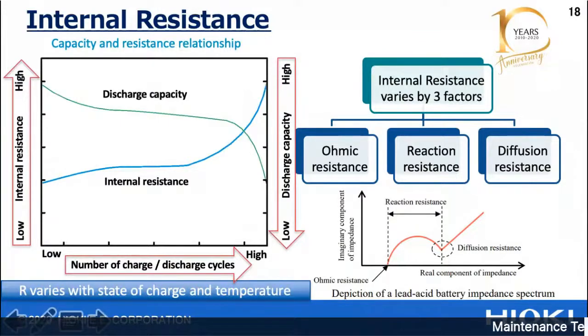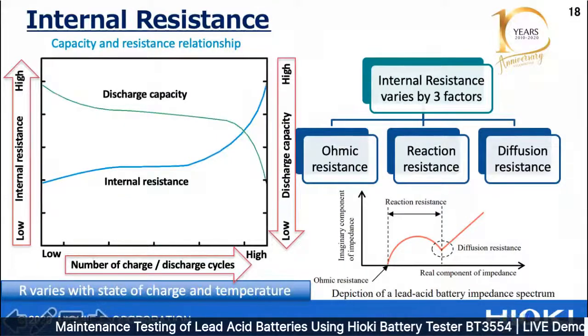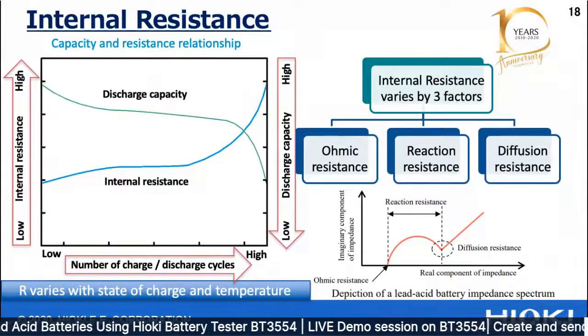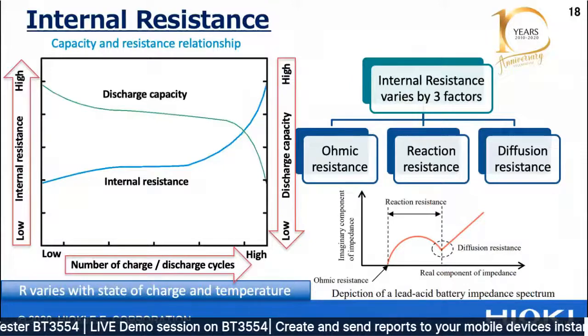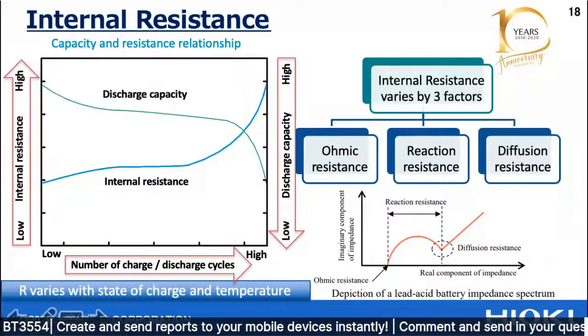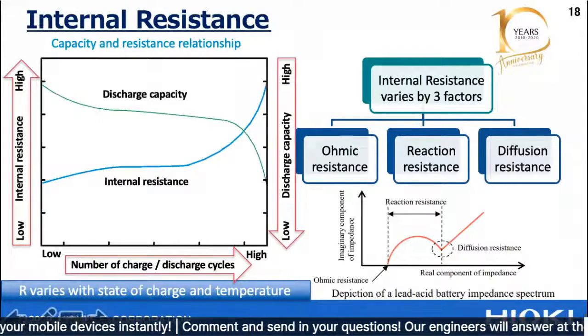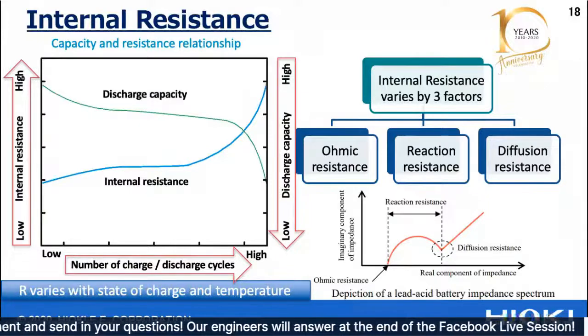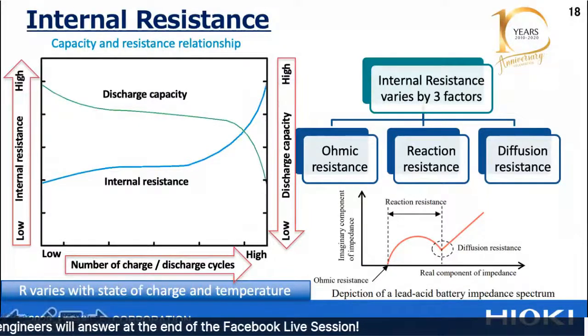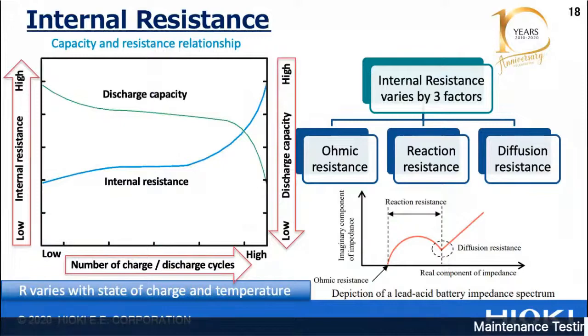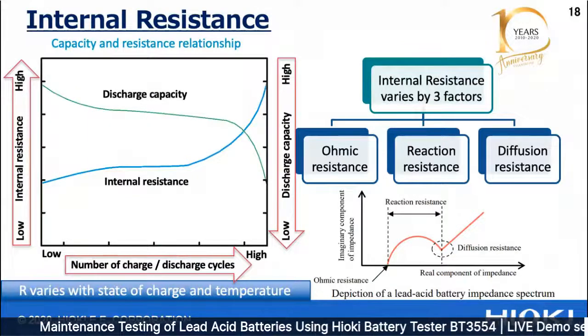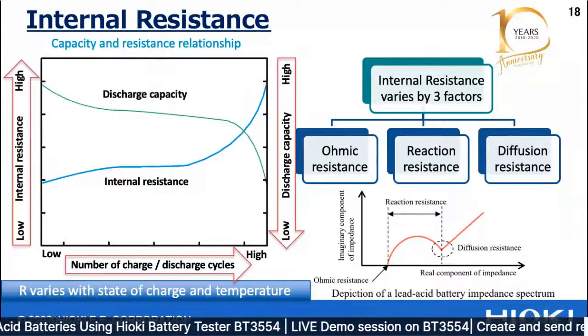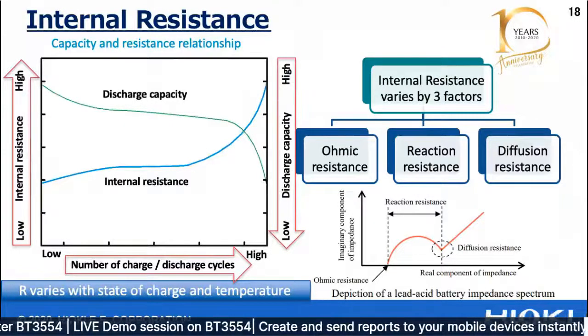The internal resistance varies based on three factors. The first is ohmic resistance, the resistance of electron conductors, such as electrode grids and terminals - this increases when there is corrosion on the grid. The second is reaction resistance, which manifests in the reaction between the active material and the electrolyte. The last is diffusion resistance, where the charge transfer resistance is caused by too many or too few ions relative to the requirements of the battery reaction. If the battery reaction progresses faster than diffusion can supply ions, there will be a shortage of ions near the electrode, preventing the reaction.